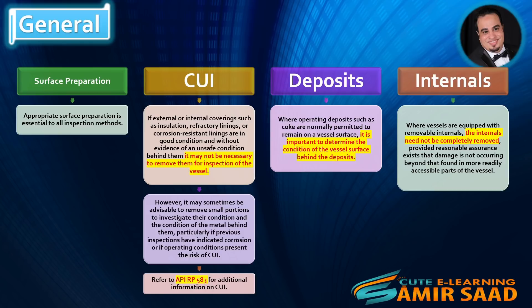Deposits: Where operating deposits, such as coke, are normally permitted to remain on a vessel surface, it is important to determine the condition of the vessel surface behind the deposits. Internals: Where vessels are equipped with removable internals, the internals need not be completely removed, provided reasonable assurance exists that damage is not occurring beyond that found in more readily accessible parts of the vessel.